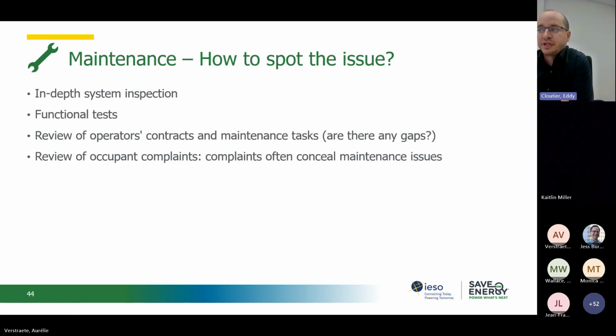So how can we detect this type of measure? First, by carrying out a good inspection of the HVAC system. It's relatively easy to detect some problems visually, such as, of course, dirty filters or coils, or even obvious mechanical problems. Next, carrying out functional tests can also help detect maintenance problems. For example, we can test the closure of a motorized cooling valve and validate whether it is tight in a few minutes by measuring the air temperature at the coil outlets. Also, carrying out a review of maintenance tasks and external contracts, if it's the case, can help quickly detect missing maintenance activities. For example, a control system where there is never any calibration of the different types of sensors. Next slide, please.